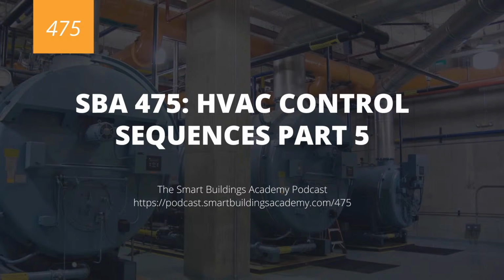But this assumes typically that the boilers are the same size and that the water is the same flow rate. This does not work so well when boilers are of different sizes and different flow rates, unless the system's designed to handle that. And the reason why is that you start to lose some efficiencies. We'll see that we do something similar to unison control in lead lag peak scenarios, but that's more so saying, hey, we're way out of our design day conditions. We really need this extra heat. And in that case, the efficiency loss is acceptable.